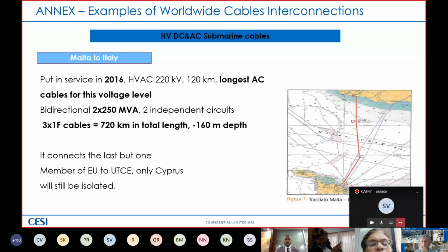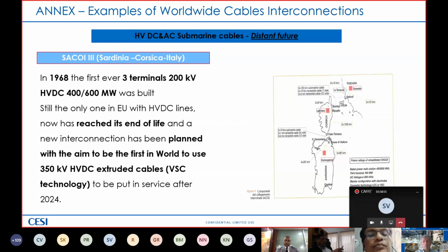Another AC interconnection is Malta to Italy, again in service since 2016. This is the longest AC cable for this voltage level, 220 kV, 120 kilometers, bidirectional. All of them I presented are bidirectional. Two independent circuits for a total of 720 kilometers. In this case, the depth is minus 160 meters. And when it happened, it connected the last but one member of the EU to the European transmission system. The only one that remained isolated till now is Cyprus. I introduced this information because in a while we will discuss another project.